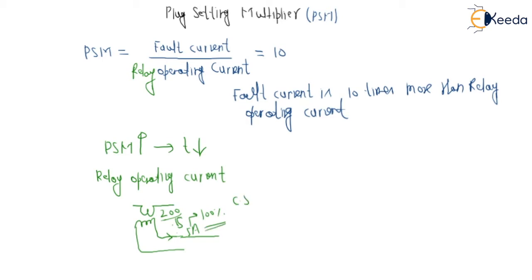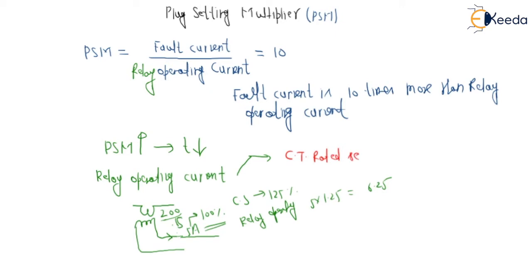If the current setting is 125%, then the relay operating current would be equal to 5 into 1.25, that is 6.25. So the relay operating current is equal to CT rated secondary multiplied by the current setting, because when the current setting changes, the operating current also changes.